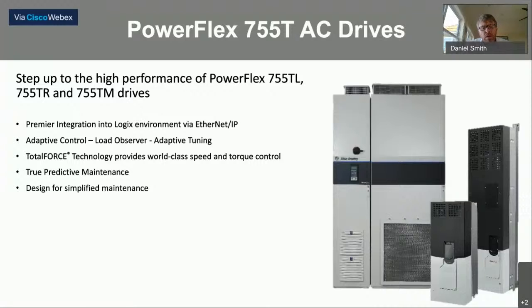The TL drive is just a low harmonics drive with an active front end. It does not have the ability to do any regenning back to the grid. But like all three of the drives, it has the ability to do true predictive maintenance, meaning that there are some algorithms written into the drive where it looks at component usage and load, how much is being used, and it can predict when it might fail, and give you a warning stating that this power component needs to be changed before failure. This fan needs to be changed before failure, and that way you can schedule downtime and have these maintenance things taken care of instead of running to failure and losing downtime.